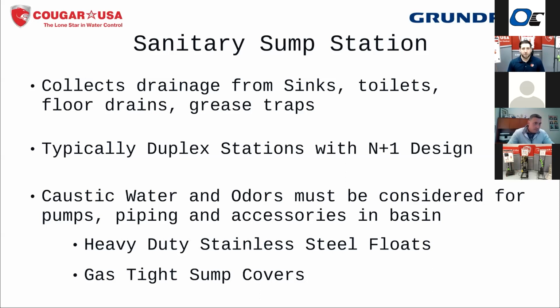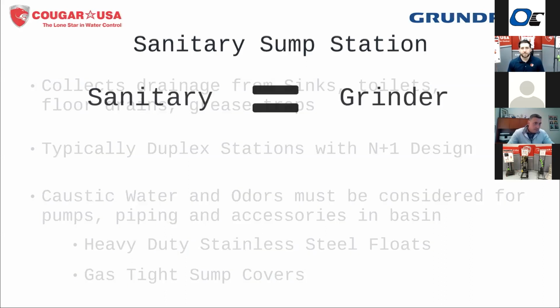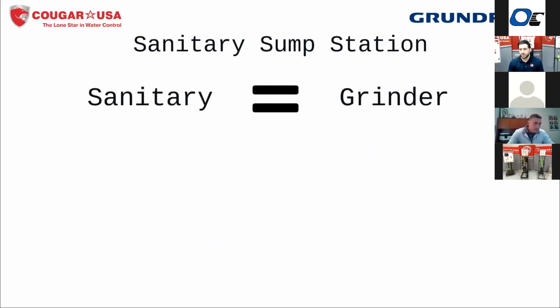It's got a Teflon coated cable, an oil resistant cable, with a Teflon coated stainless steel float. It's going to give you a lot longer life in those conditions, as well as having the gas tight covers, which again I've got an example of, that are going to seal in those odors and not allow them to seep out into the room or into the rest of the building or the outside air. Okay.